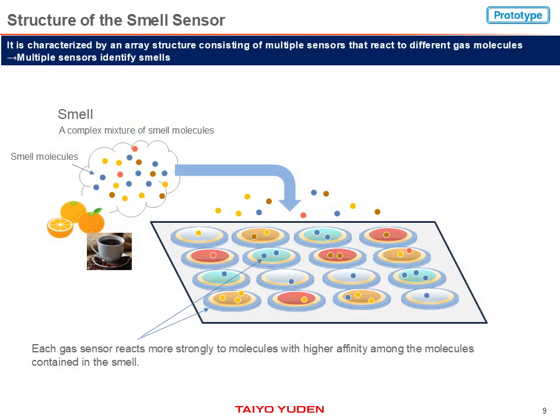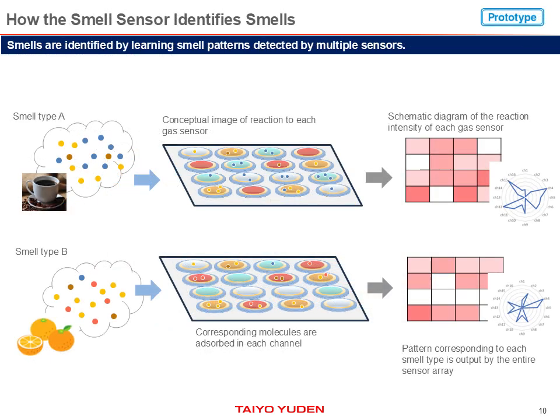To detect smell, multiple sensitive membranes are prepared for sensing. The QCM type uses 16 types of sensitive membranes to detect smells through 16 channels. Molecules of different smells adhere to the sensitive membranes differently across the 16 channels. This diagram shows that the same sensor responds differently to type A smell and type B smell. This difference in response is learned by machine learning to identify smells.